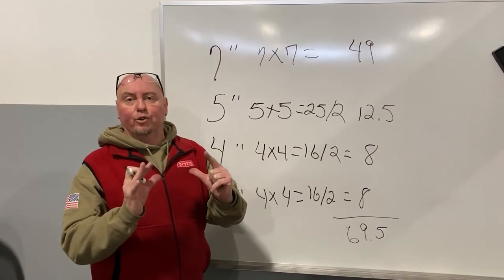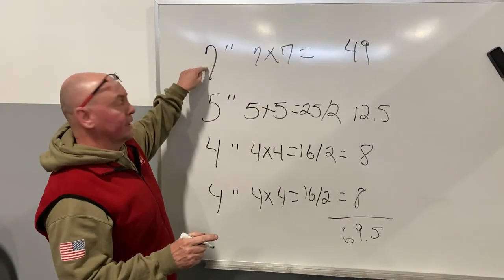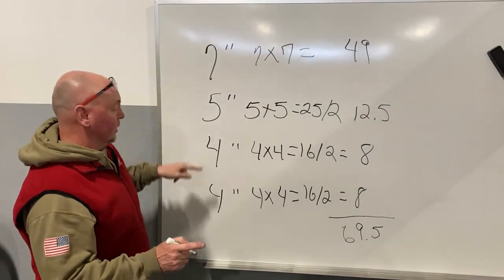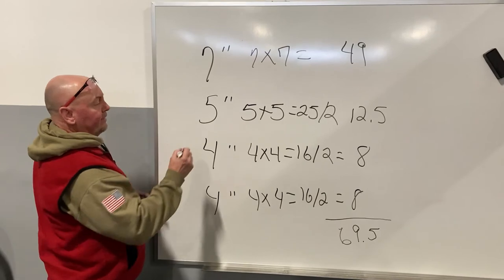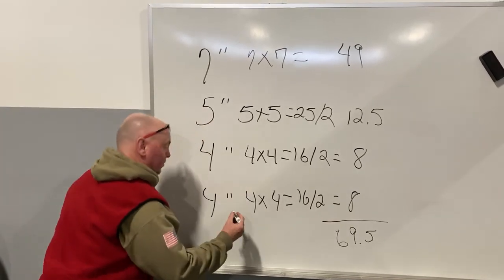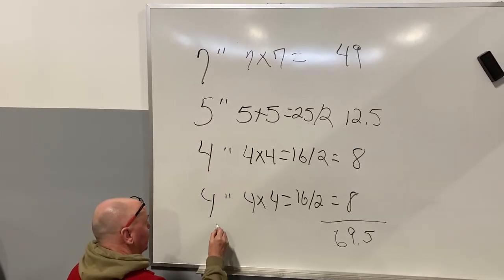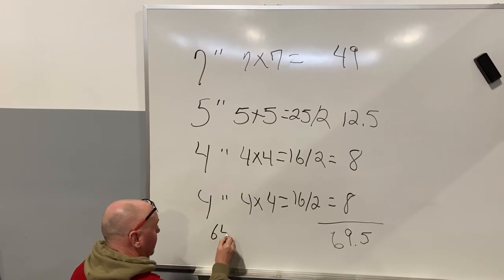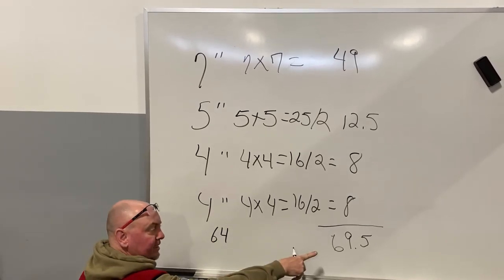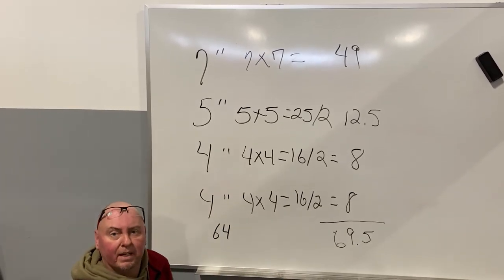So now I need a pipe larger than that. So I know it's going to be bigger than this, right? So what's the next size? 8 inch? 8 times 8 is 64. 64 is less than 69.5, that pipe ain't big enough.